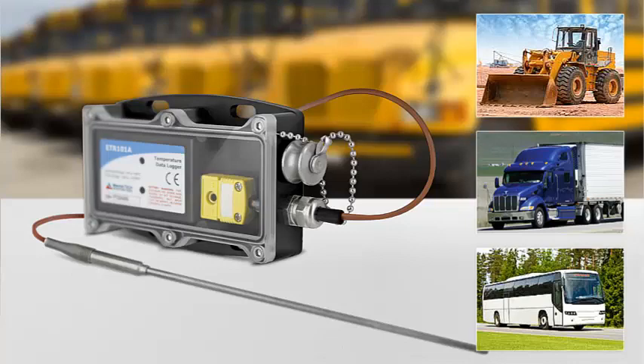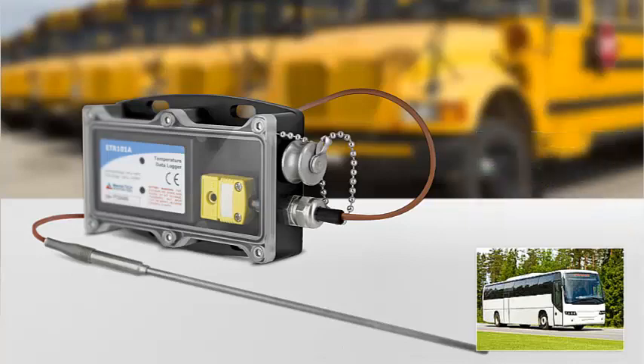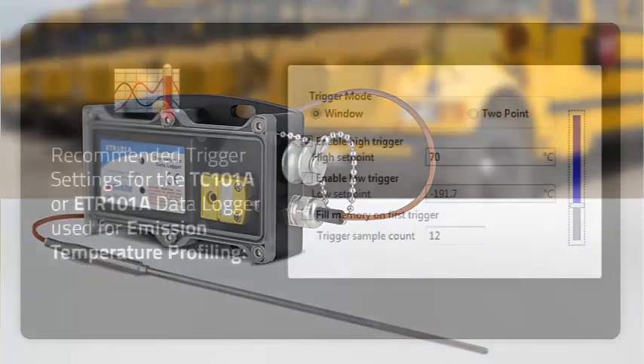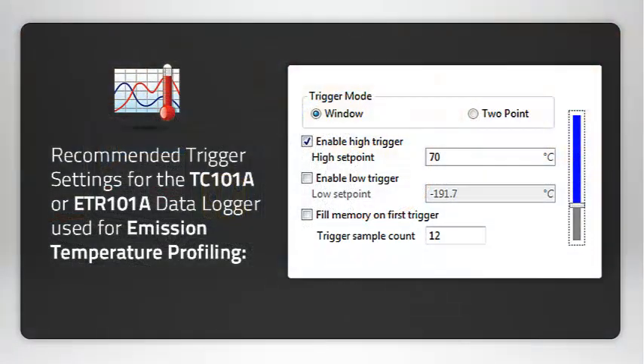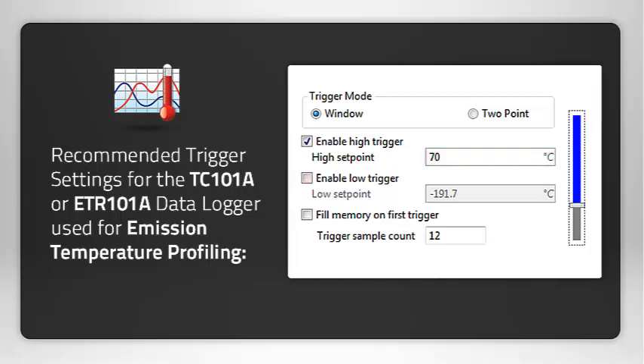To accomplish this, the user will select Window Mode with a high trigger enabled and set point value of 70 degrees Celsius. The user chooses to leave the low trigger disabled and sets the trigger sample count to 12. These settings will give the user the necessary data for this application.